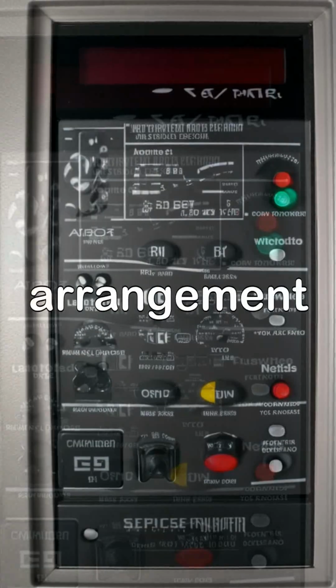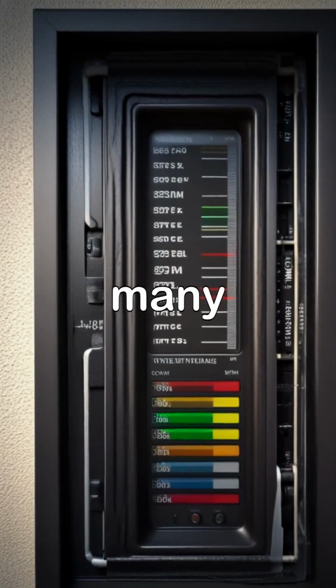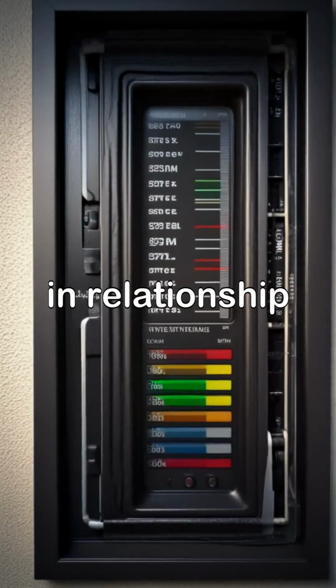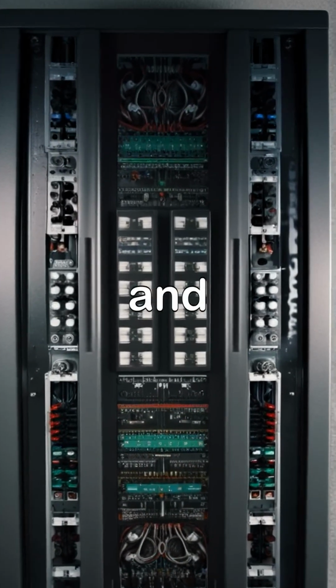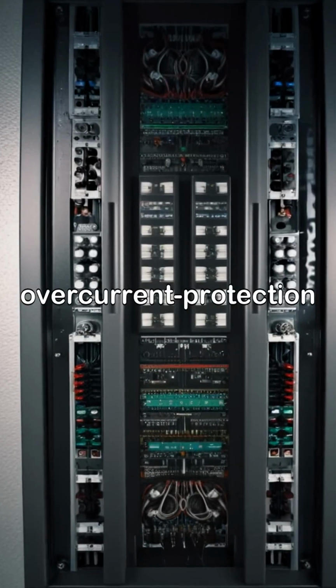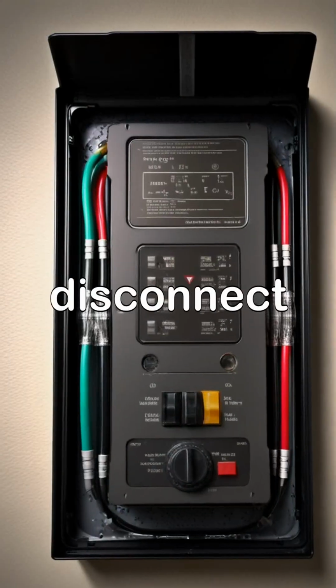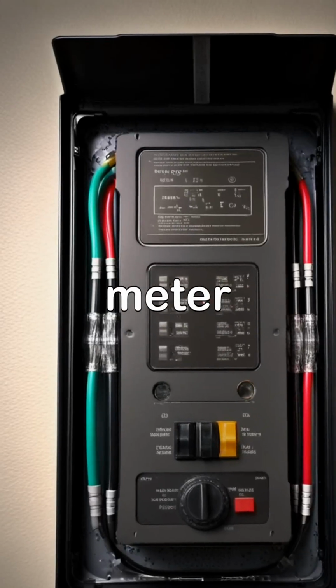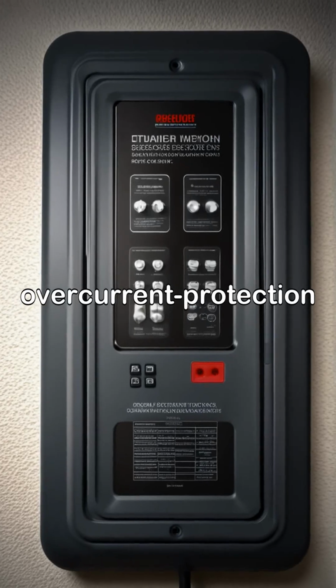It would be convenient if all service equipment and every service arrangement were exactly the same, but they're not. There are many types of panels and many acceptable ways to locate them in relationship to the meter. The common denominator among panels is that each must be grounded and contain a main disconnecting means and a main overcurrent protection device. The main disconnect is wired to the load side of the meter and can mechanically turn off all the power in your house. The main overcurrent protection device can automatically turn off all the power to your house.